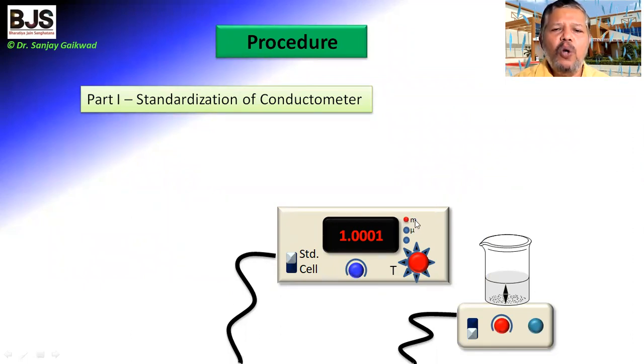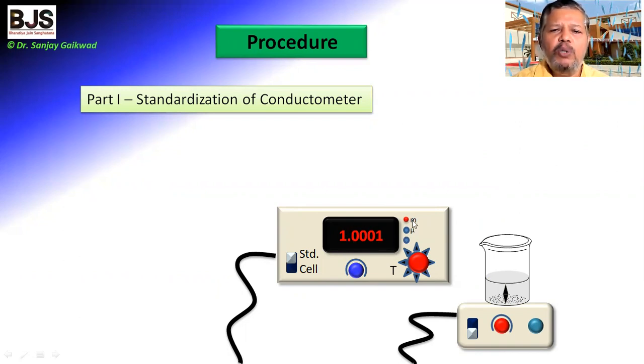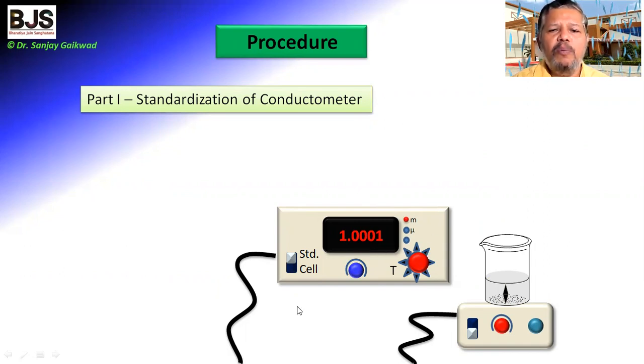When the indicator light is at 'm', that is milli, the value is × 10⁻³. If the light is at micro, the value is × 10⁻⁶. The displayed value is 1.0001 × 10⁻³, meaning the conductometer is standardized. If this value is not displayed, then with the help of the adjustment knob, we can set this value, and after adjustment, once this value is displayed, the conductometer is standardized.